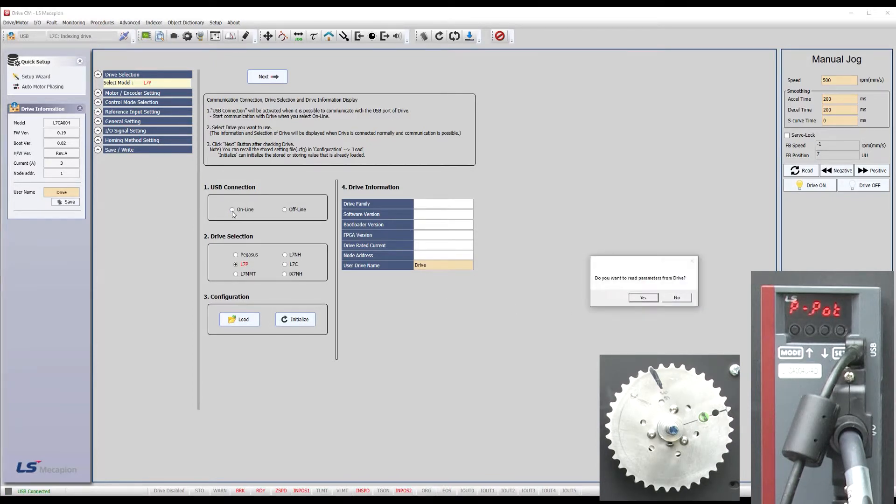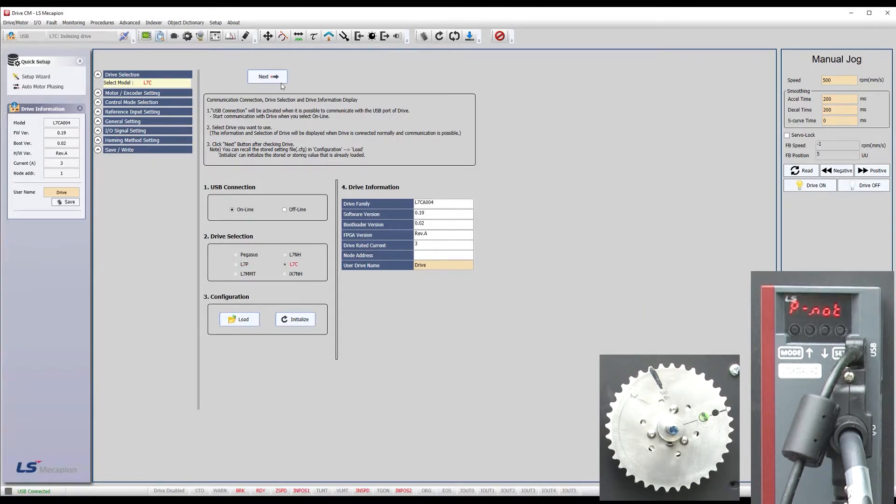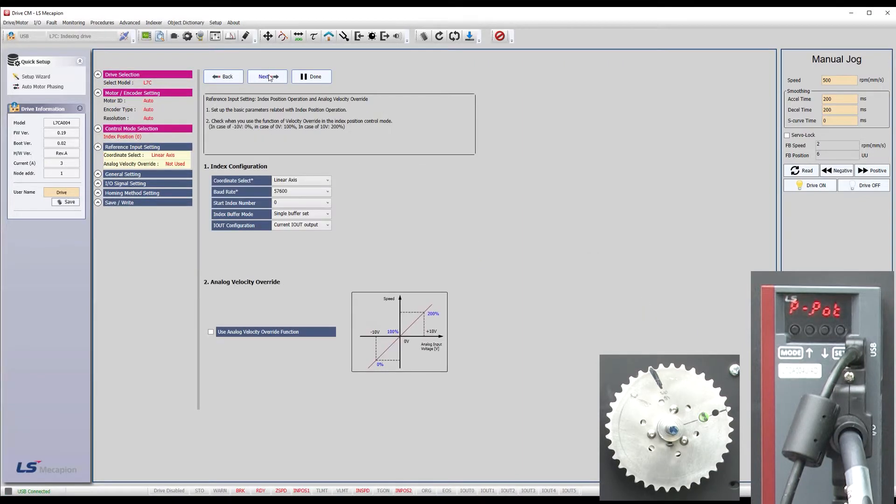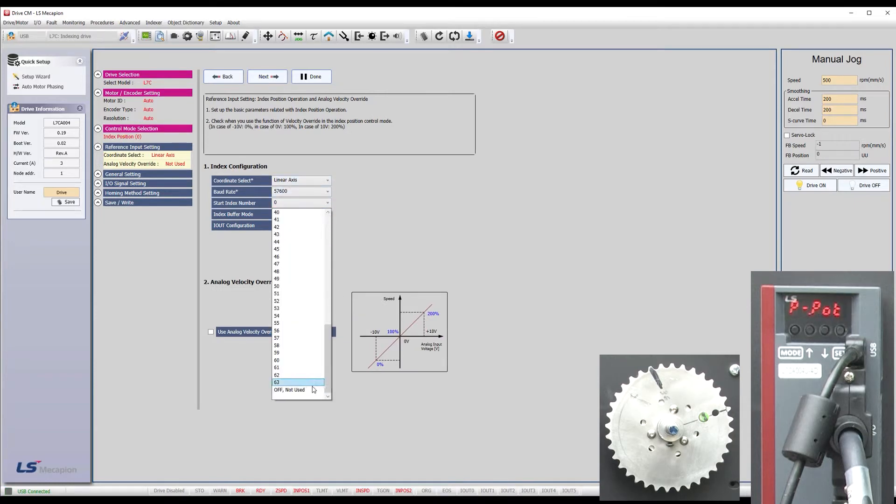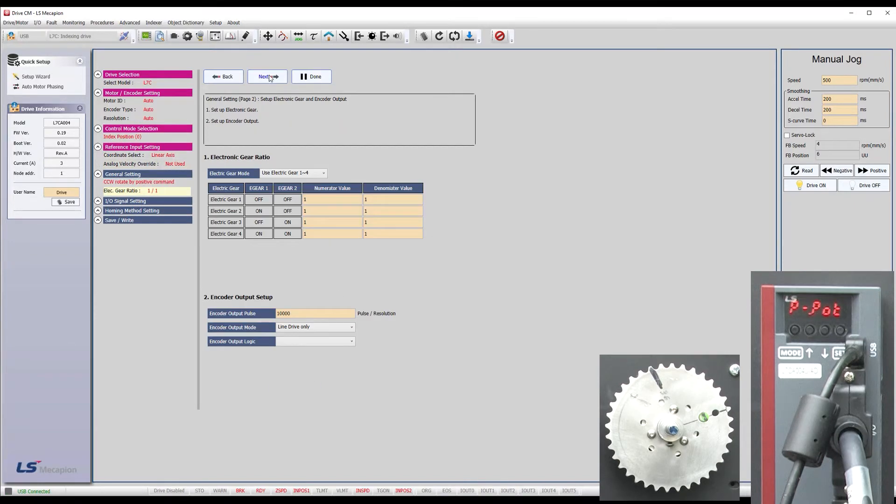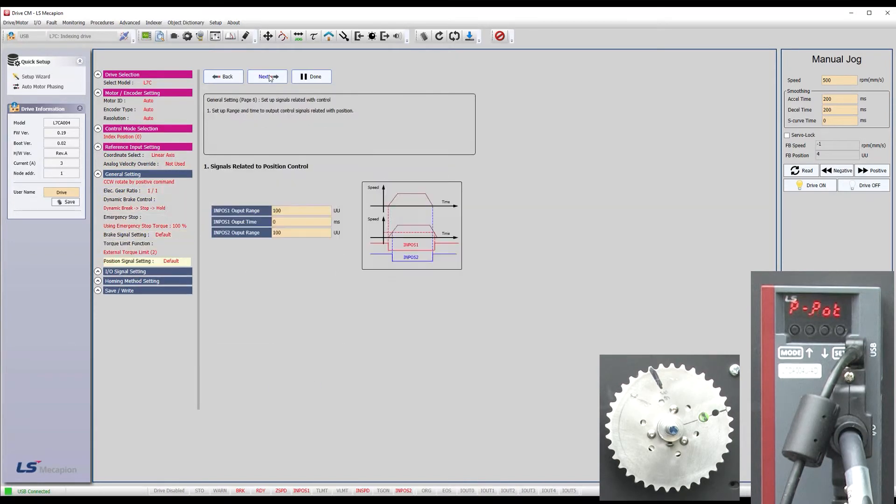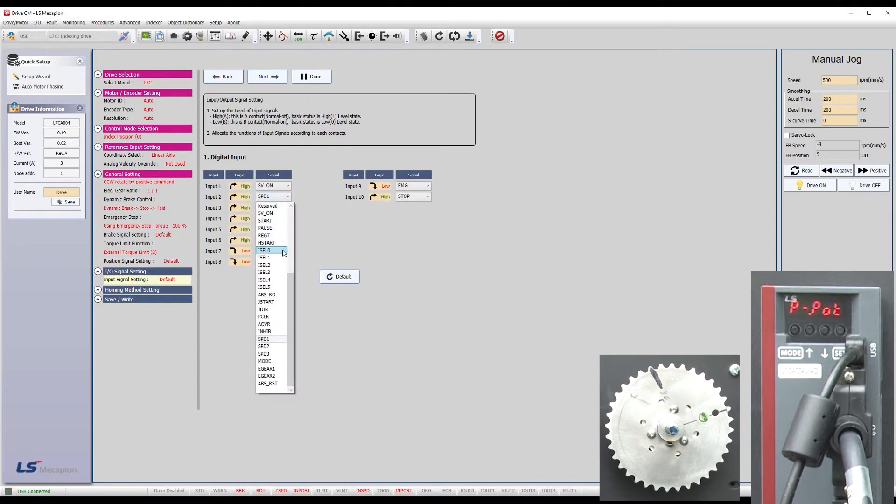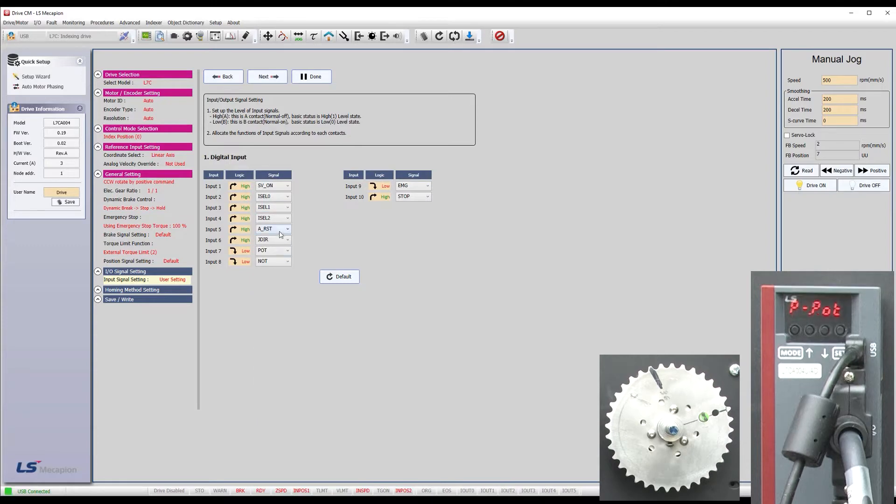Yes, we want to read the drive's current configuration. We want indexing mode and we will control indexing from the digital inputs so we will turn this off. All of this is fine and for digital inputs we want a servo enable. We will use the first three index selectors and we will need a start and a stop.